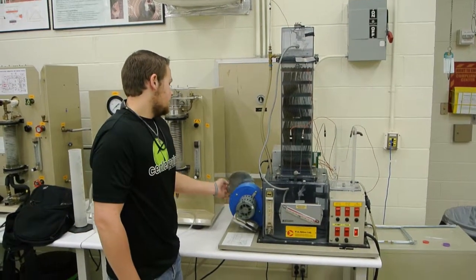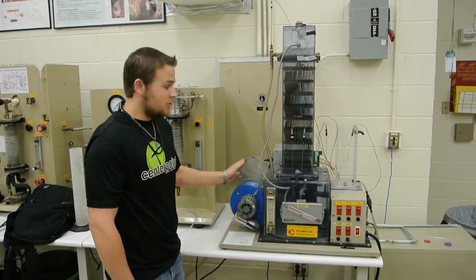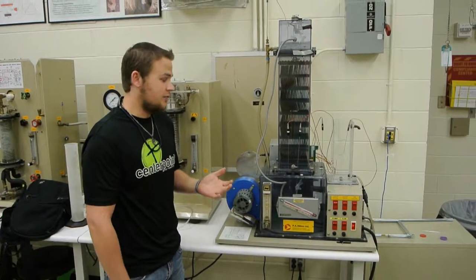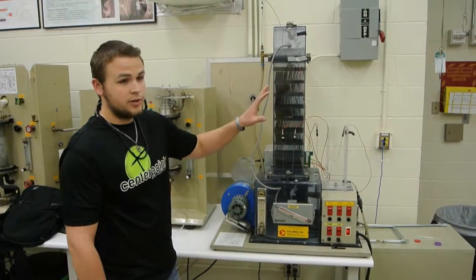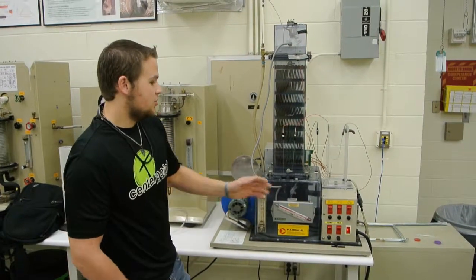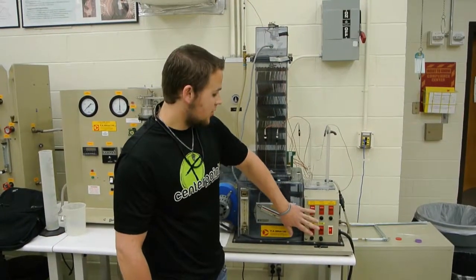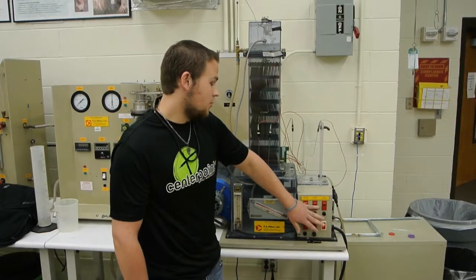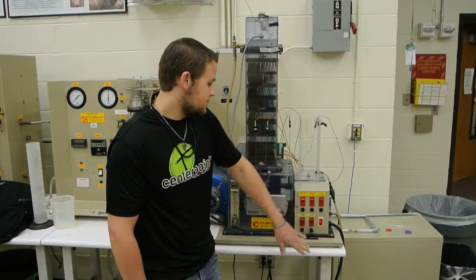You'll then open up the disc and allow for maximum airflow. Another 7 minutes should be taken to allow for steady state, and you'll take all pressure readings. After this, you'll go in and start turning off all components. You turn off the 0.5 kilowatt and then the 1 kilowatt power source. You also turn off the pump and the fan, and then you're done.